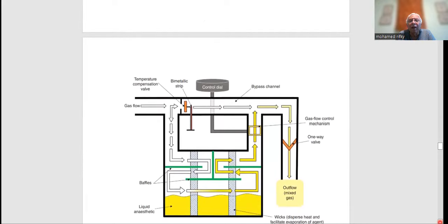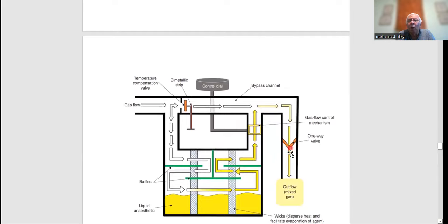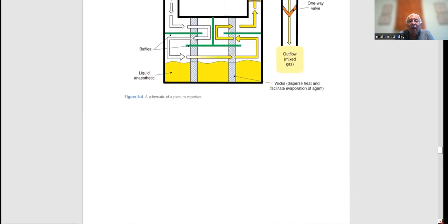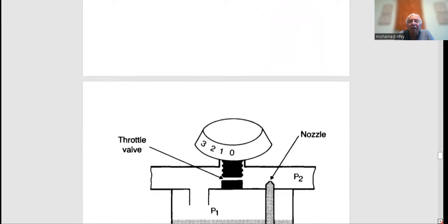This is the normal vaporizer. We have an additional one-way valve so that the retrograde flow, as you said, from the pumping effect will not be affected. And this is the baffle system which directs the fresh gas flow to go through the surface of the liquid anesthetic so that it increases the surface of vaporization. This is the bimetallic strip controlling the opening, and this is the bypass, and this is the path that's going through the vaporizer.